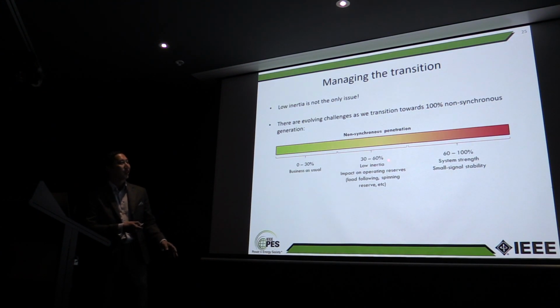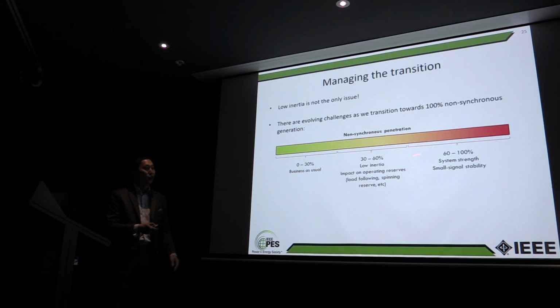However, as we increase that and go up towards 60 to 100%, there are other emerging issues that come up. System strength is an issue. System strength is really about short circuit capacity at any point in the network. We are starting to replace synchronous machines, which have lots of short circuit power, with inverters, which are all current limited and don't produce that much, so all of a sudden we have lower system strength. Protection devices may not work, and we may need to make them work better. We also have voltage instability as a result of that. So that's an issue that's coming up.